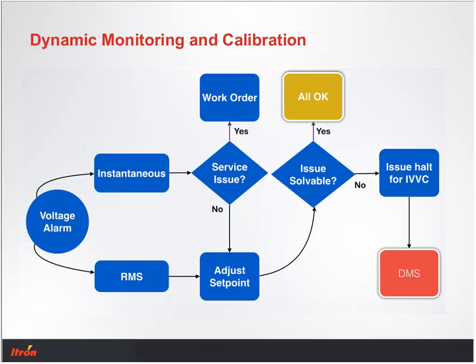If the issues we find with voltage are solvable, then everything's cool. We make our adjustment to the set point on the DMS for the feeder and move along. But if we can't solve the problem, our biggest concern is providing quality power to the customer, so we issue a halt to the IVVC, which stands for Integrated Volt Var Compensation, which we've recoined voltage optimization at Avista.